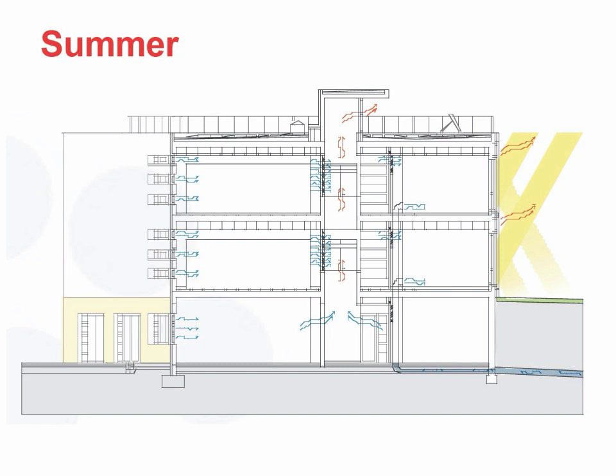In summer, use shading and exterior cavity ventilation to keep out south-side heat. At the clerestory at the top, there's an overhang for shading. Stack ventilation goes from the edges in through the louvers, up through the atrium, and out through the top exterior clerestory. On the lower right, you can also see air coming in underground through what we might call an earth tube or earth-air heat exchanger — so fresh air brought into the building even when closed can be pre-cooled by passing it through the ground.